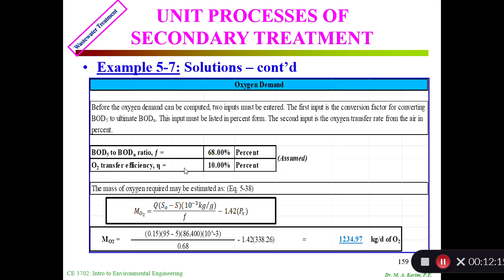Before the oxygen demand can be computed, two inputs must be entered. The first input is the conversion factor of BOD5 to BOD ultimate. The second input is the transfer rate of air, percent of oxygen transferred to air. I consider BOD5 0.68 and the transfer efficiency is 10%. That means 10% of oxygen from the air would be transferred to the water as dissolved oxygen, because microorganisms cannot take any oxygen that is not dissolved. Mass of oxygen required may be estimated using equation 5-38. I get 1234.97 kg/day of oxygen.